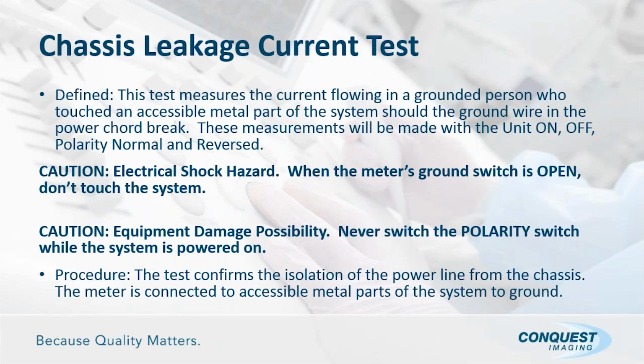So after we've got our ground resistance, we're going to move on to the chassis leakage current test. And this is a really important one. The test measures the current flowing in a grounded person who touched an accessible metal part of the system should the ground wire in the power cord break. So these measurements will be made with the unit on, off, and the polarity normal and reversed. This complicates things quite a bit.